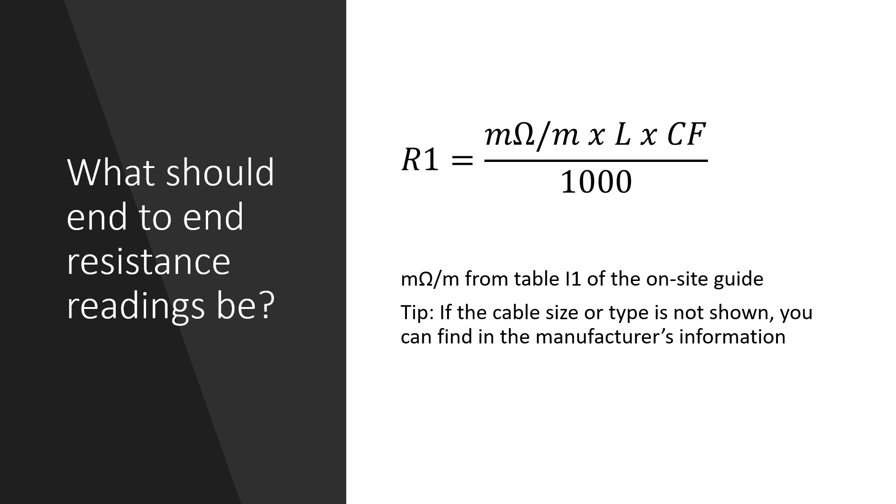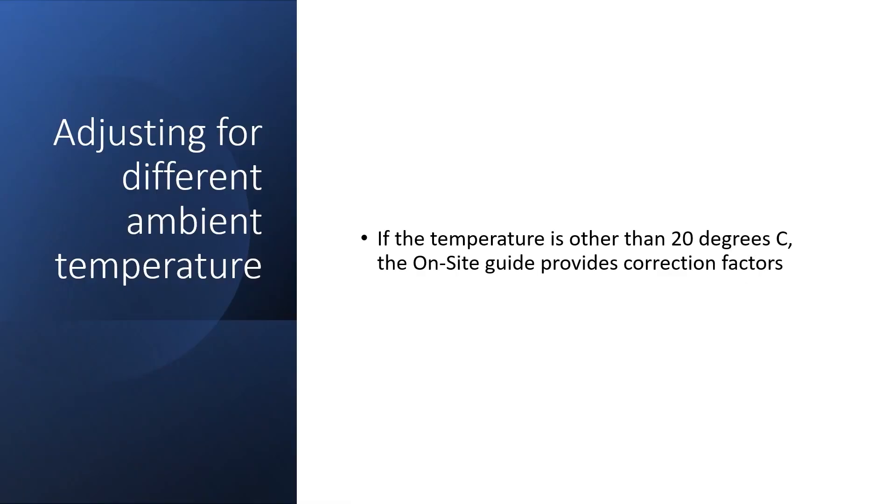The values on table I1 are based on an ambient temperature of 20 degrees C. If the ambient temperature is other than that there are correction factors on table I2 for 5 degrees, 10 degrees, 15 degrees and 25 degrees. For 20 degrees the factor is 1. If the ambient temperature is not shown on the table then there is a formula below that which shows how to adjust for different temperatures.